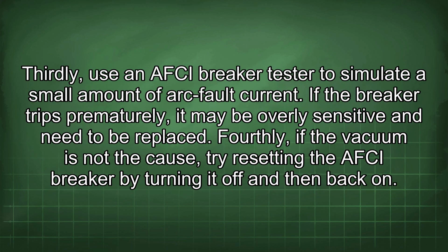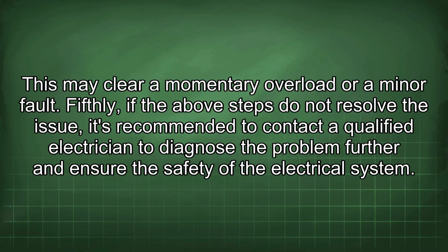Thirdly, use an AFCI breaker tester to simulate a small amount of arc fault current. If the breaker trips prematurely, it may be overly sensitive and need to be replaced. Fourthly, if the vacuum is not the cause, try resetting the AFCI breaker by turning it off and then back on. This may clear a momentary overload or a minor fault. Fifthly, if the above steps do not resolve the issue, it's recommended to contact a qualified electrician to diagnose the problem further and ensure the safety of the electrical system.